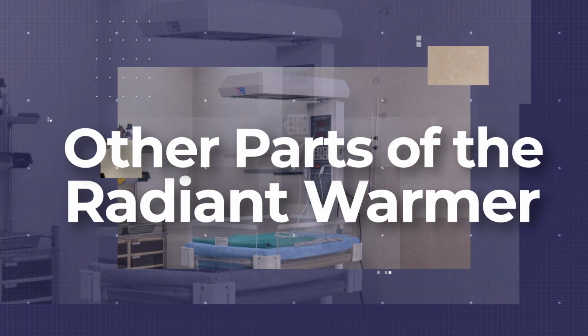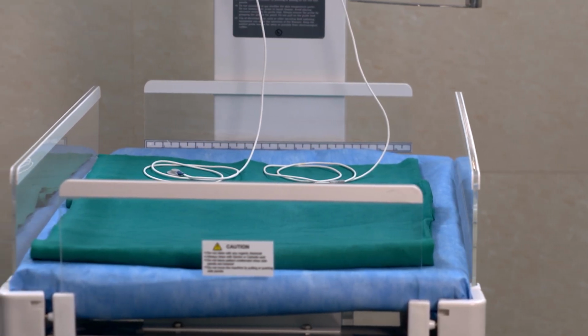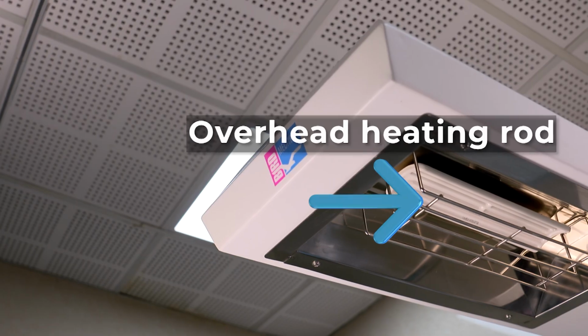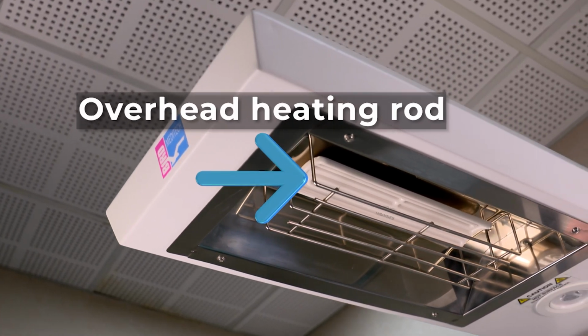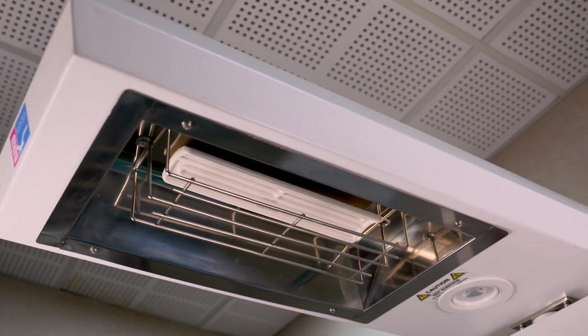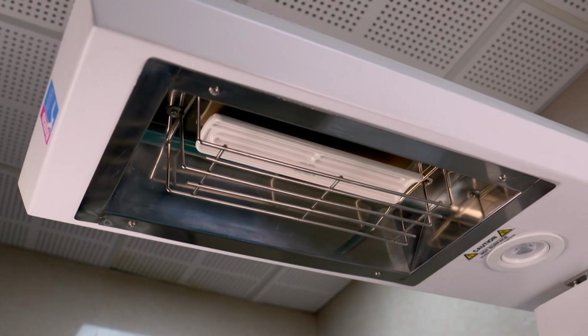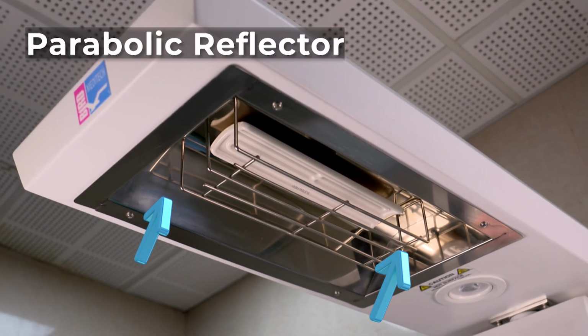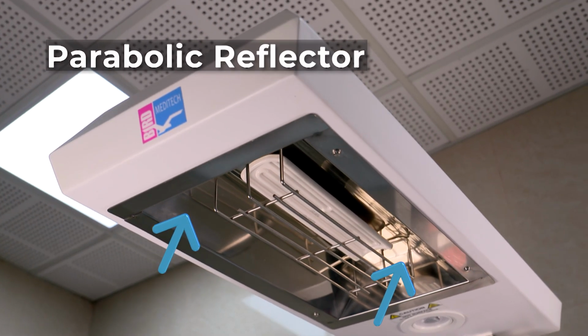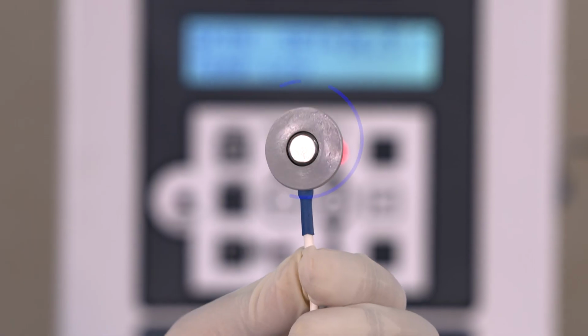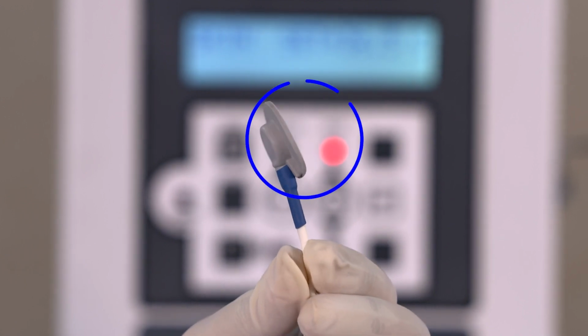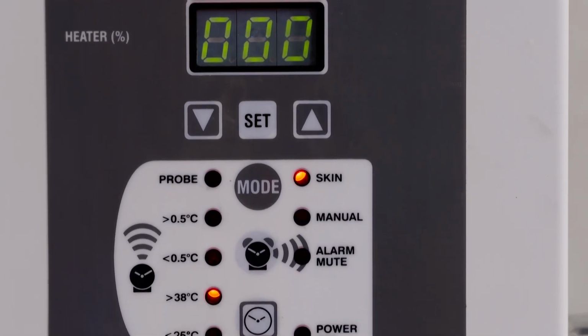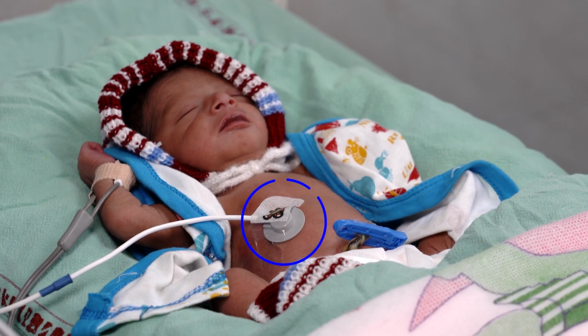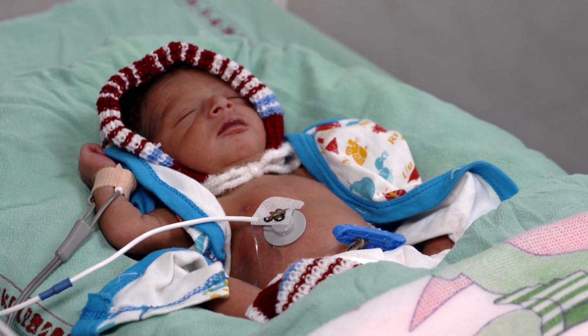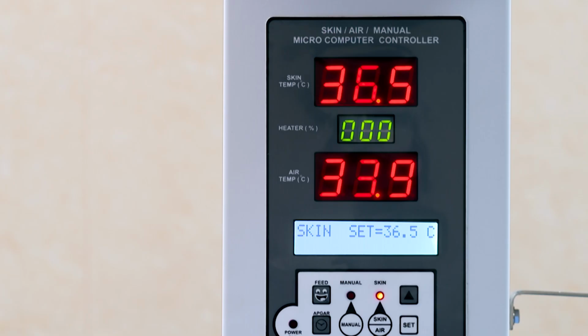Other parts of the radiant warmer consist of bassinet for placing the neonate. The overhead heating rod is made of ceramic or quartz element to provide radiant heat which is reflected by the parabolic reflector onto the baby in the bassinet. The skin probe is to be used while the baby is kept under servo mode. It is attached to the baby's skin at the right hypochondrium to record the temperature of the neonate.